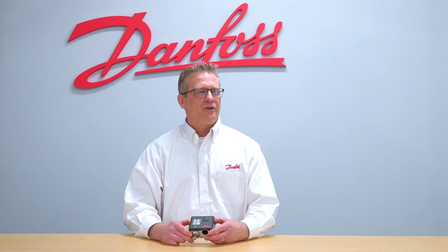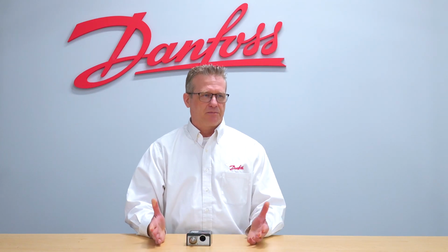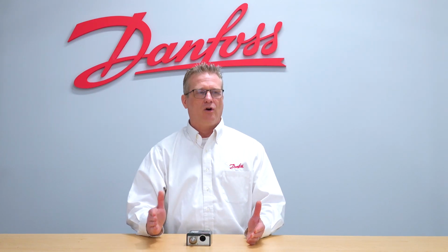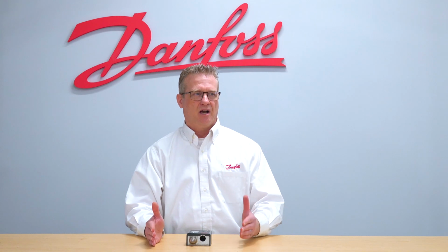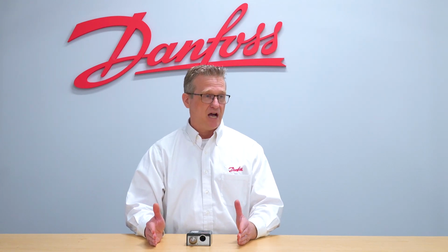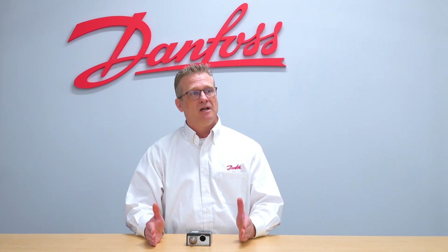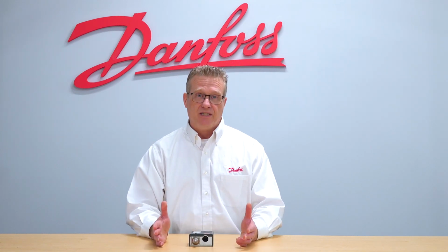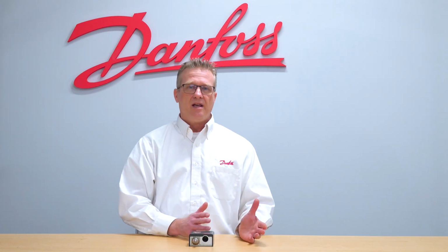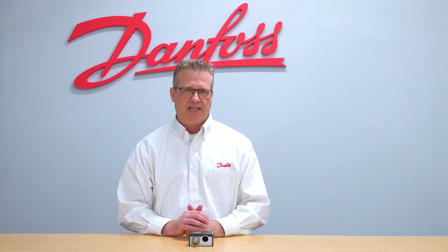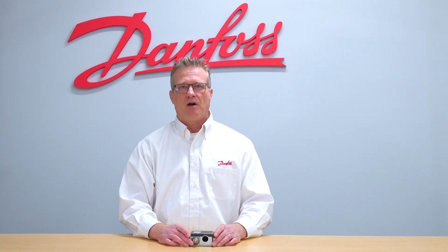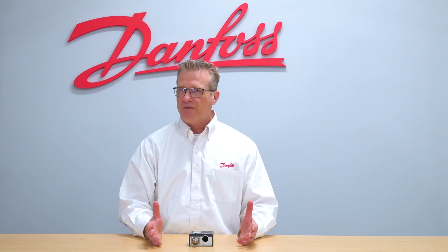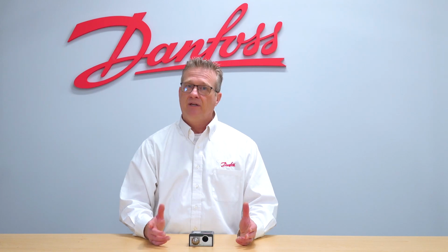What the pressure control does is it is set for a specific pressure where it will open and stop something, and then another pressure value, which is called the cut-in value, that is used to bring it back on again. Some of these are automatic reset. Reset means when the contacts will change position again. So if it's automatic, it will automatically close the contacts and bring back on again whatever it stopped.